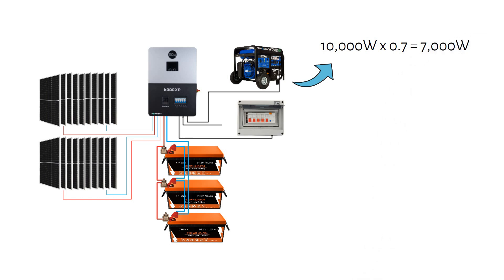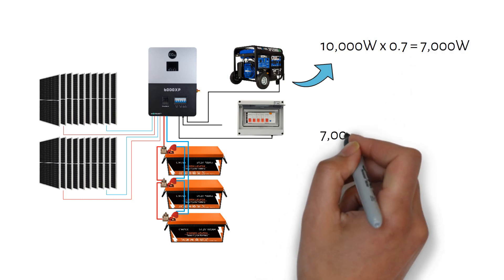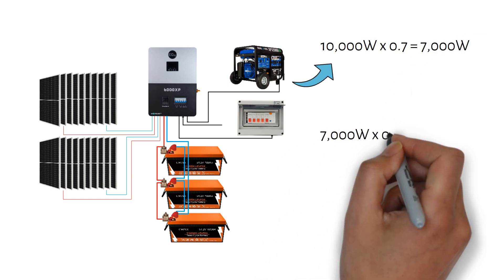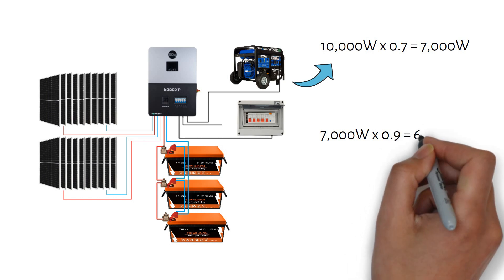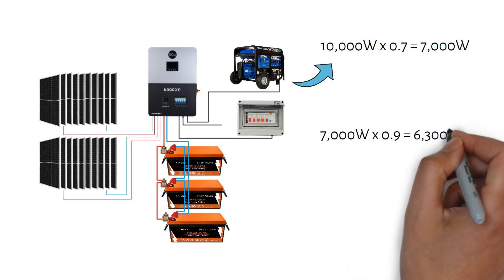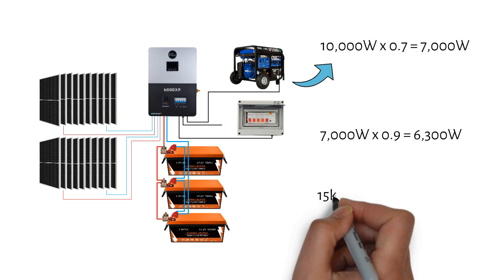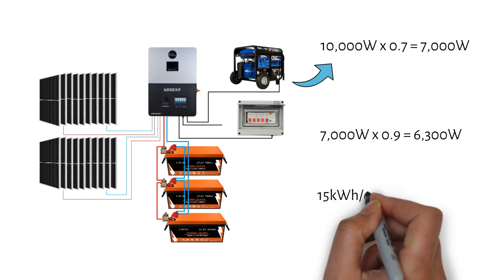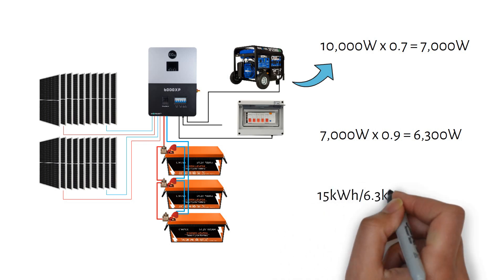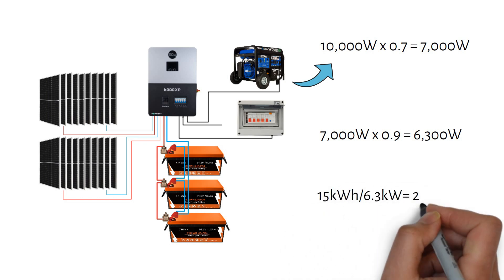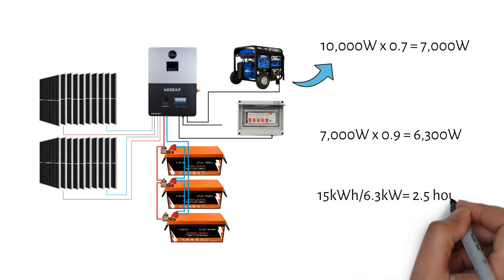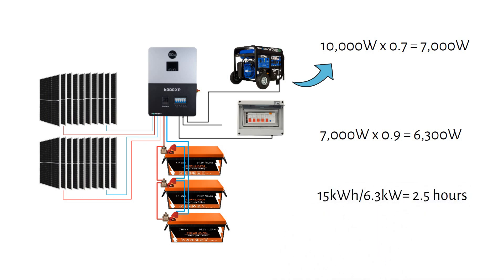Considering a charging efficiency of 90%, this means the system will charge at 6.3kW. To recharge a 15kWh battery at 6.3kW, it will take approximately 2.5 hours.